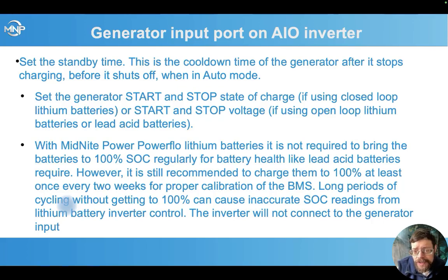If you're using voltage as your controls, say an open loop lithium battery or a lead acid battery instead of our batteries, then you're going to have voltage controls instead of state of charge controls. With the MidNite batteries, like we said, we don't have to get them up to 100% regularly, but you want to think about keeping the BMS in calibration. So think about that when you're setting your stop state of charge, what you want to do with that. Start state of charge, like we discussed, I usually recommend around 25%. You can go lower, but depending on the situation, it may not really be worth it.